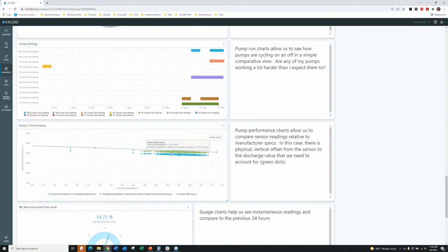But just to say, I needed to add in a little extra head, or in some cases subtract a little extra head. And really what that has done is push up that data series from the raw readings to what the system actually should be. It is showing me that my pump is actually really, really close to this curve, whereas the raw readings might cause me to think that I had some impeller degradation because we're dipping below the manufacturer curve.